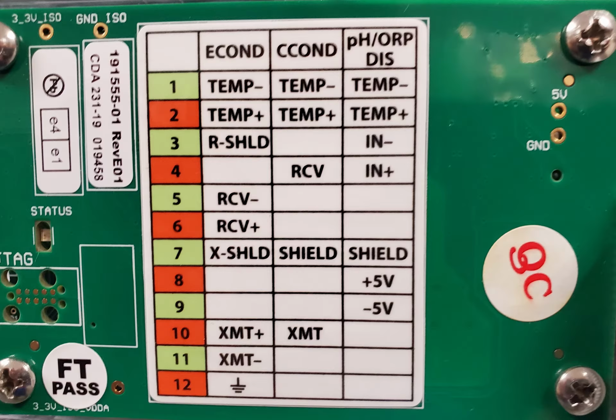To determine how the sensor is wired to the controller, the user will need to look at the sticker on the front of the sensor input card. This sticker shows all of the sensors get wired to the controller. In order to determine how the boiler sensor is wired to the controller, look at the one labeled CCOND. Here you will see that the boiler conductivity sensor can have a total of 5 wires if it has ATC, or automatic temperature compensation. They will be labeled Temp Plus, Temp Minus, RCV, XMT, and Shield.